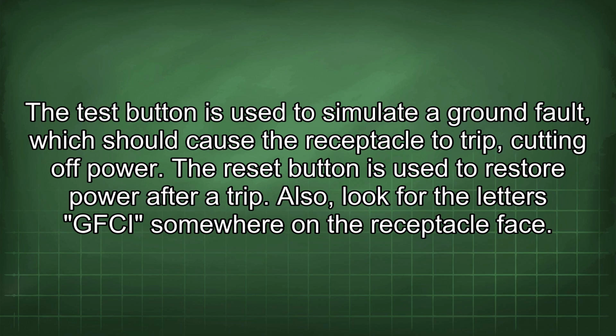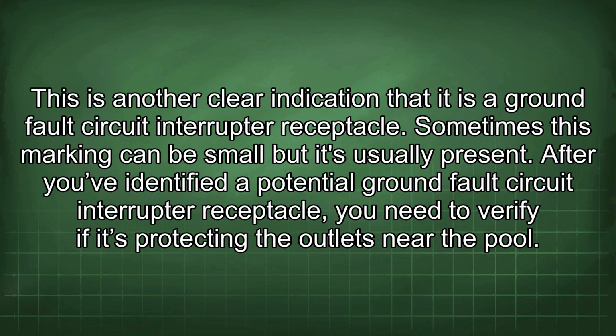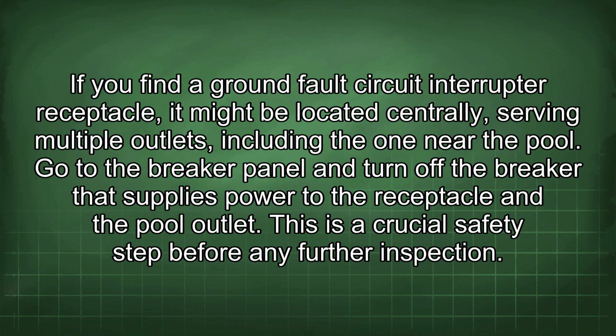Also, look for the letters GFCI somewhere on the receptacle face. This is another clear indication that it is a ground fault circuit interrupter receptacle. Sometimes this marking can be small, but it's usually present. After you've identified a potential ground fault circuit interrupter receptacle, you need to verify if it's protecting the outlets near the pool. If you find a ground fault circuit interrupter receptacle, it might be located centrally, serving multiple outlets, including the one near the pool.